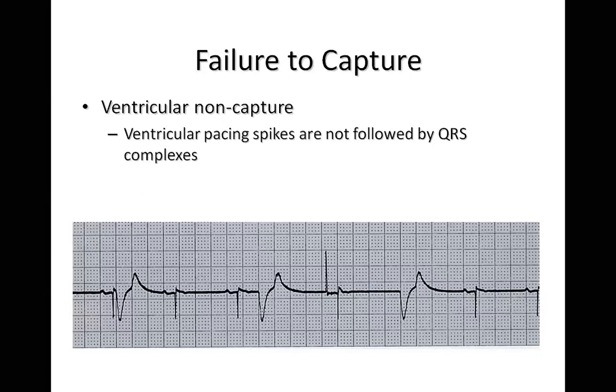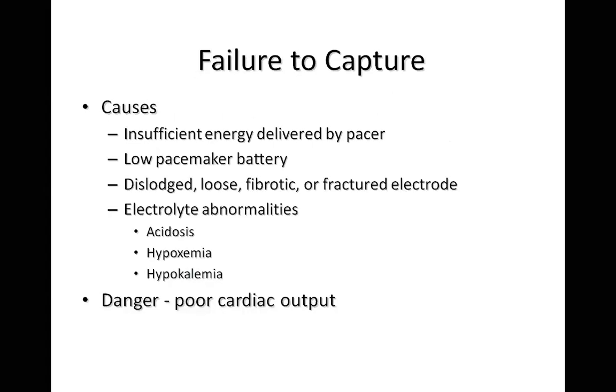All right. So there are many reasons for failure to capture. It could be that the leads are dislodged, meaning that you are just seeing pacing spikes. And the moment the lead dislodges, the battery will be emitting a lot of energy, thinking that the energy it was issuing was not sufficient to cause depolarization. So, as we explained before, it will be increasing the energy, increasing the energy, increasing the energy. And the problem will be that it will be consuming the battery, because the higher the quantity of energy you use, the faster you consume the battery.